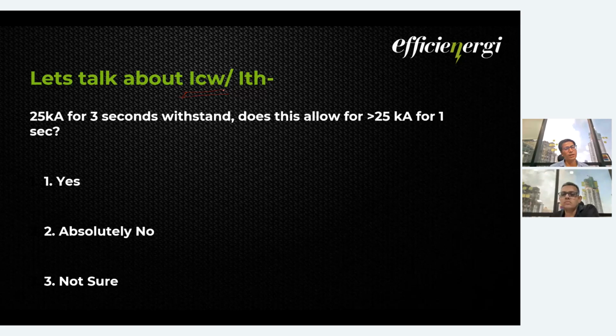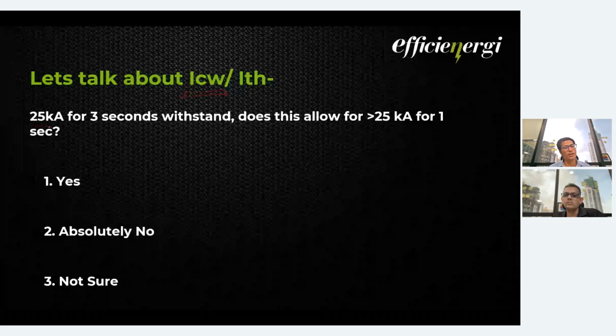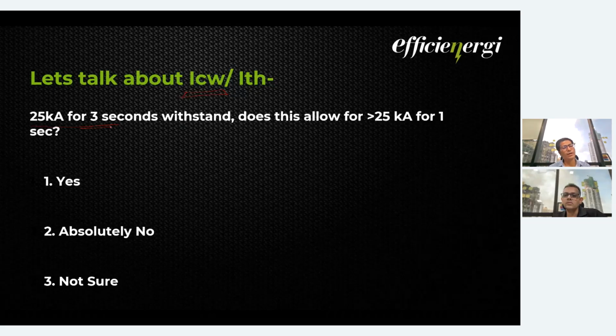Okay, so ICW, as I said, the breaker manufacturer, let's say in this example, claims 25 kiloampere for 3 seconds withstand. Then 25 kiloampere will pass for 3 seconds, and there will be no damage to the breaker contacts, no damage to the insulation of the breaker. Small pittings are allowed, but no major damage is allowed in this test. So this is basically the ICW.